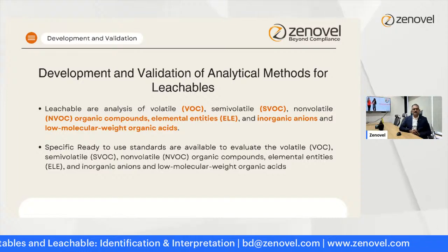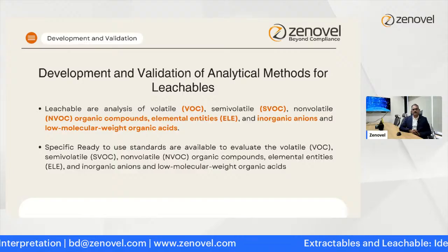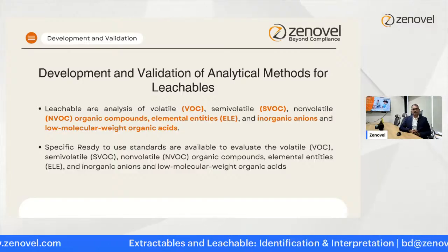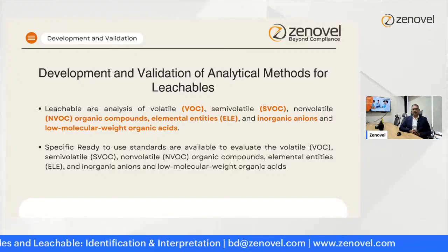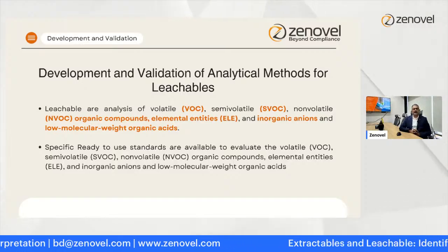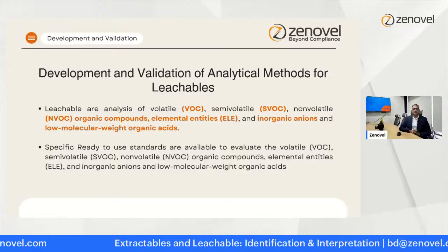Leachables analysis covers volatile organic impurities, that is VOCs, semi-volatile organic impurities, SVOCs, non-volatile organic impurities, elemental impurities, inorganic anions, and low molecular weight organic acids.